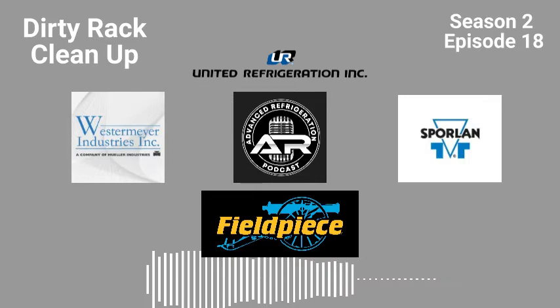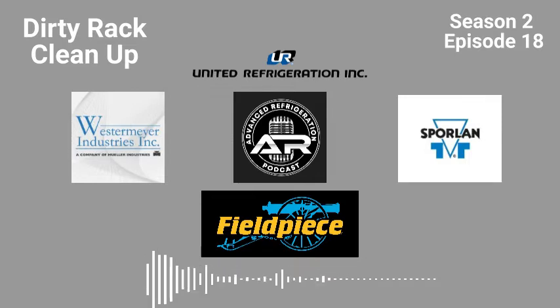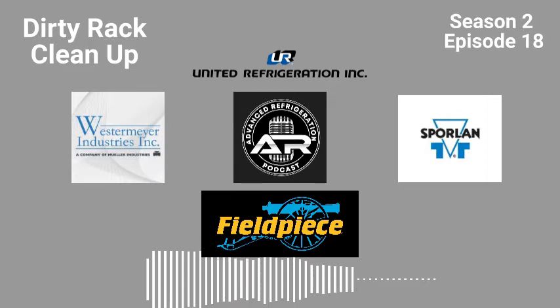If you've got a strainer, and obviously most supermarkets should have a Sporlan valve with a strainer built into it or a removable strainer, there's no point in having a dryer at the case. Dryers belong at the rack where they're serviceable, where you don't have to break out a torch and burn on a dryer in a case or walk-in. I want to be able to clean a screen in 10 minutes. It's 10 minutes versus 2 hours. Do you not agree?